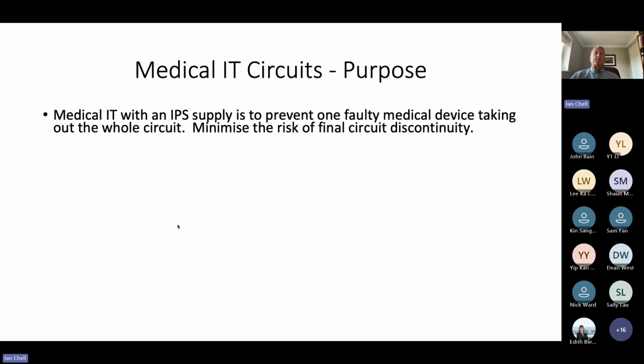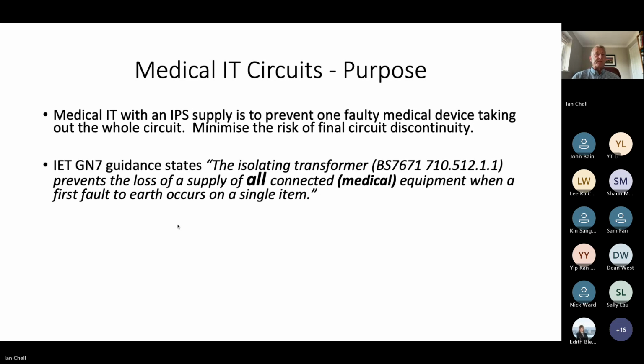So the purpose of medical IT circuits is to prevent one faulty device taking out the whole circuit. Okay. Now, some of you may think, is it really? It is to minimize the risk of final circuit discontinuity. And guess what? In Guidance Note 7, it does actually say that. If you read it in detail, that's what it does. It just stops one device disconnecting the loss of supply from all other connected medical equipment.